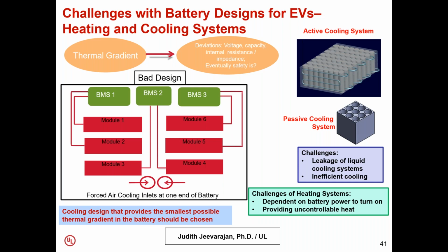It was a truck battery where they had 6 modules with a BMS, with 3 different BMS units monitoring different modules and balancing them, but there was no central BMS actually monitoring all of the slave BMSs. They had a forced air cooling system going from one end of the battery to the other, and what they found was that modules 1 and 6 were getting very hot, especially in a cold environment when it was snowing outside.